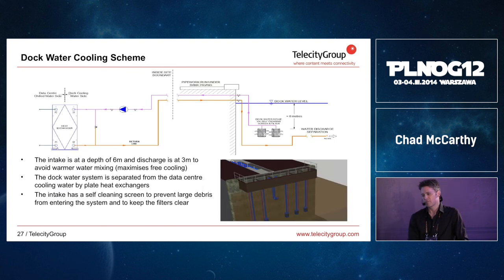This is a very simplified schematic of how the system works. The diagram on the bottom right, you can see at very low level on the three-dimensional drawing, that is effectively the intake connection at a depth of 6 meters. We draw the water into the data center, it goes through a heat exchanger, and then it's returned to the dock. It's just a simple circulation process. What's not shown on the schematic is that we do also remove heat from the data center first and supply it to the apartments in the form of district heating. So the amount of heat that people don't want, so we can't use it, for example in the summer condition where people aren't looking to heat their apartments, then we have a larger heat contribution that goes into the heat exchanger and into the body of dock water.